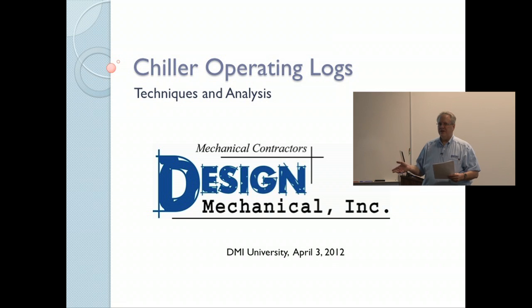Now, this presentation is going to focus mostly on water-cooled chillers, although it's just as important to log air-cooled chillers. And again, these are just some sample logs, and just because it's a Trane chiller log may not be applicable to all Trane chillers. That was a Trane centrifugal chiller log. I believe I had a sample Carrier screw chiller log on the back side of that.